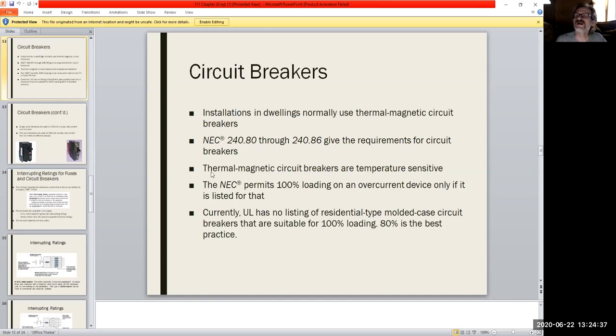So they're old school. It's a mechanical, thermomagnetic circuit breaker. As the current rises, the spring tension becomes greater and greater until finally, if it's a 20 amp and it reaches 25 over a given amount of time, it'll start to flex, and then it stays on over that time, and it goes boop. Again, it's all time rating. They could make it a shorter time, but then you would have to be turning your circuit breaker on every time you turn the vacuum cleaner on or something like that. So this is why it always takes a second before it trips, and yes, it will.